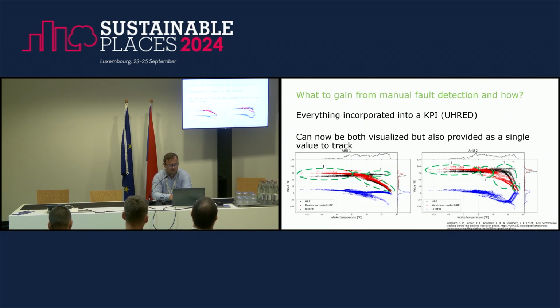So it's what we see in case 3, where it becomes clear that we are recovering more heat than we need, which can lead to basically one of two cases. Either we will be supplying a higher temperature out from the air handling unit than we would like, or we will need to apply cooling to it in order to reach our target, and that's of course not desirable. So in this case, there's definitely room for optimizing the performance or the control strategy of the heat exchanger. So this one was for the operational personnel directly.